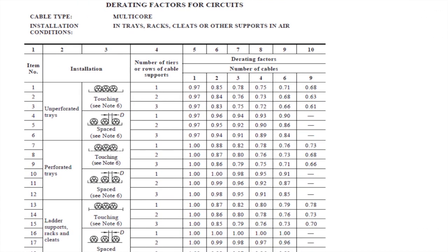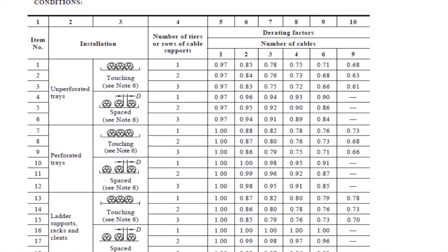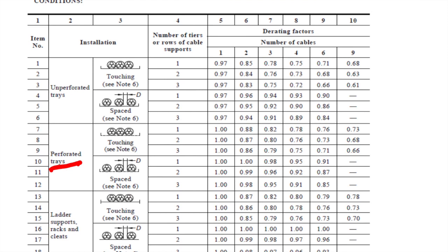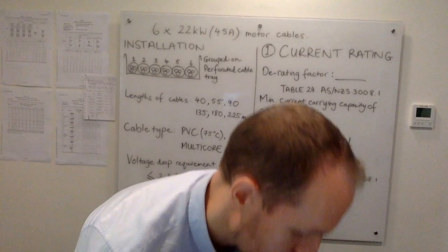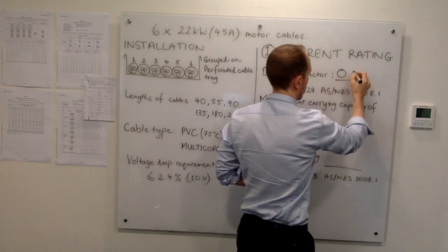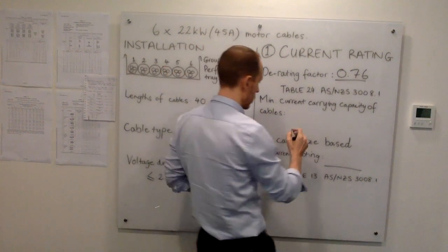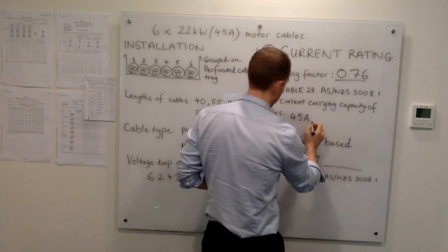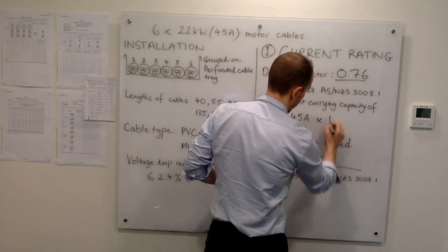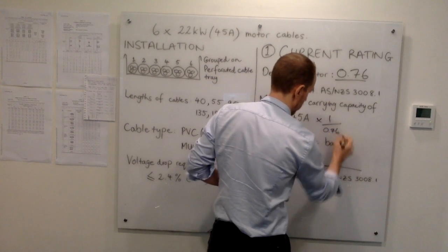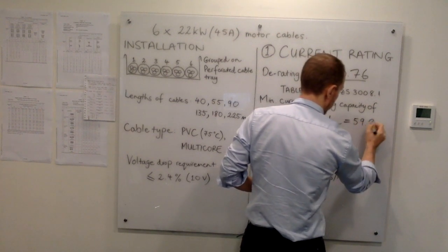This is table 24. We're using perforated trays, cables will be touching, number of tiers is one, and we've got six cables grouped. Therefore, we're going to use a derating factor of 0.76. The minimum current capacity of the cables required is 45 amps multiplied by 1 over 0.76, which is 59.2 amps.